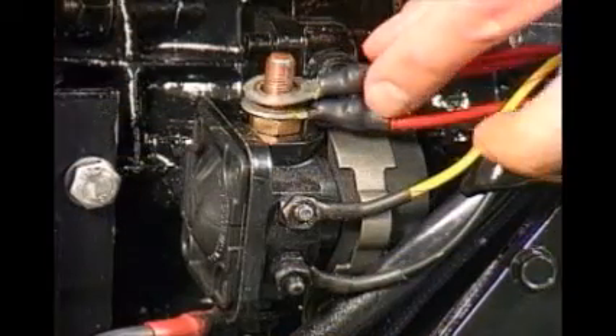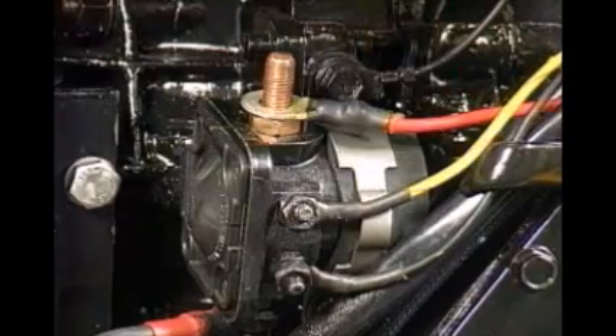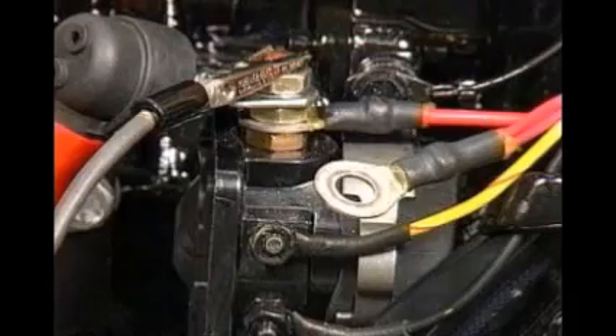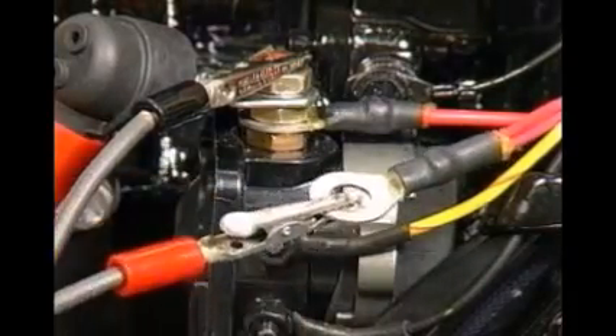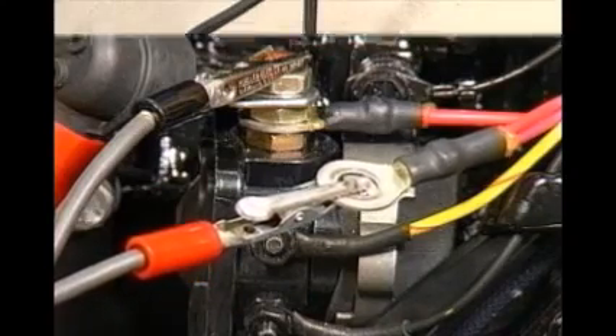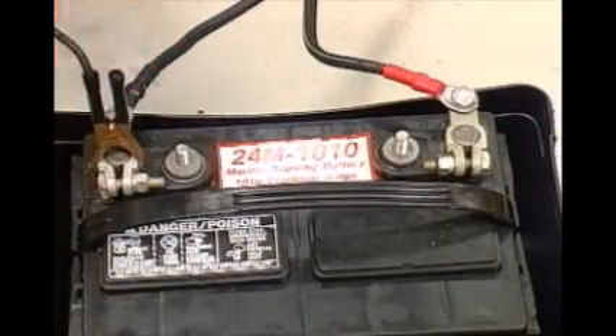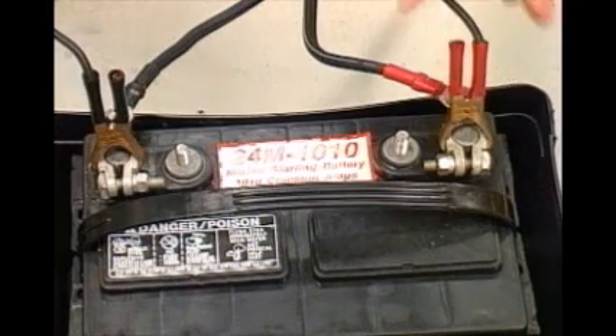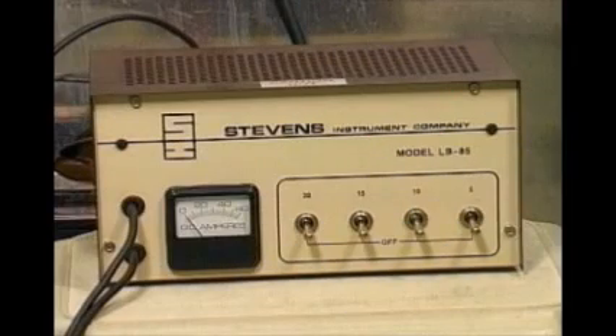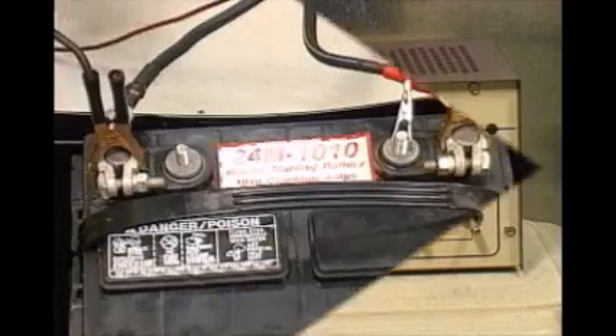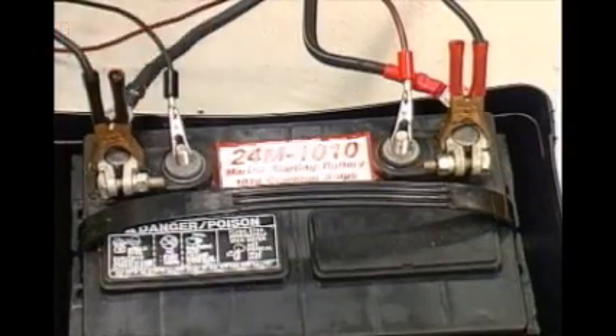Disconnect the red output lead between the rectifier regulator and the starter solenoid. Connect an ammeter in series with the red lead and the battery side of the solenoid. Connect a variable load tester or carbon pile resistor across the battery terminals. If the tester does not have a built-in voltmeter, connect a voltmeter across the battery terminals.